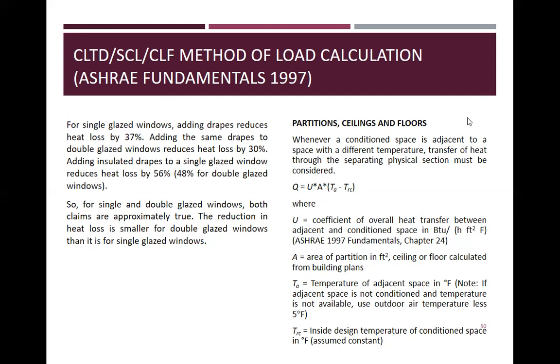T sub O is the temperature of adjacent space in Fahrenheit. Note, if adjacent space is not conditioned and temperature is not available, use outdoor temperature less 5 degrees Fahrenheit. If the adjacent temperature is the same as the inside design temperature of conditioned space, so that is 0. Okay. T sub RC is equal to inside design temperature of conditioned space in degrees Fahrenheit, assumed constant.